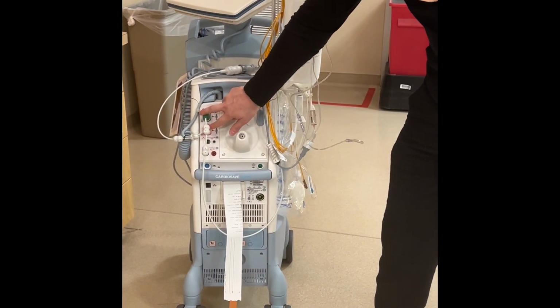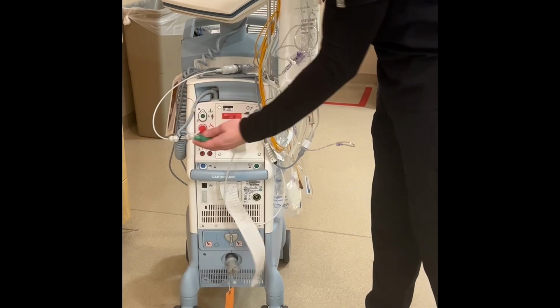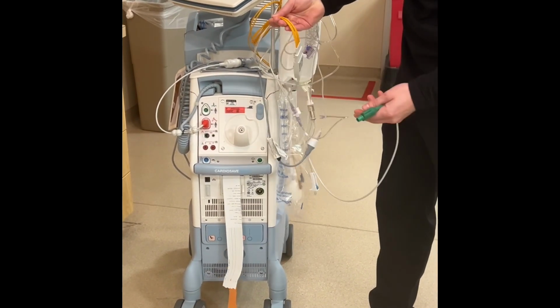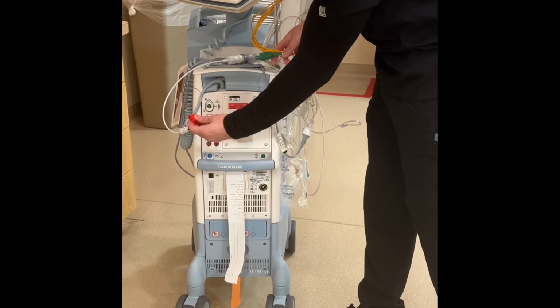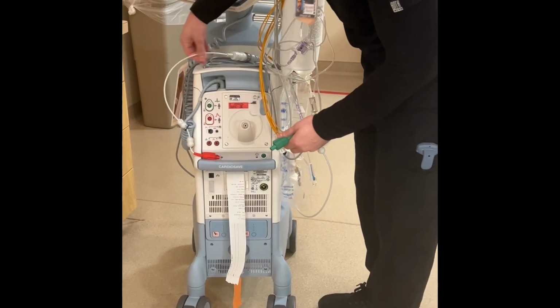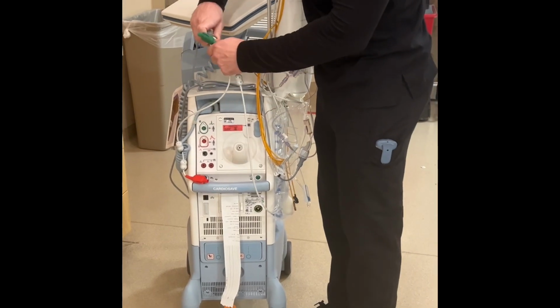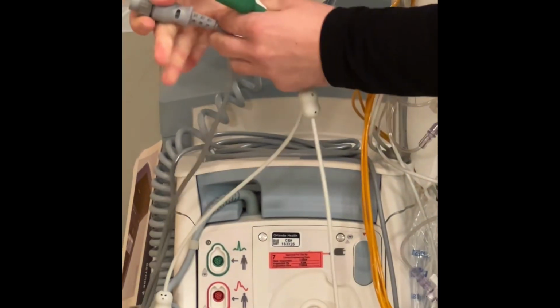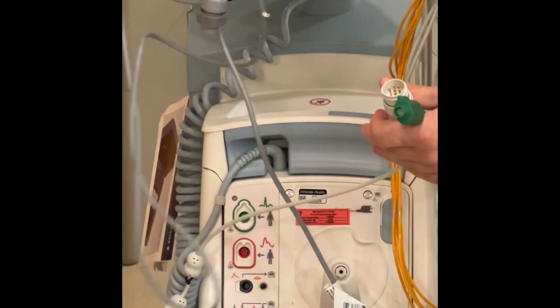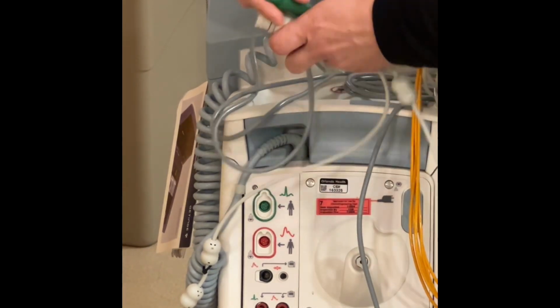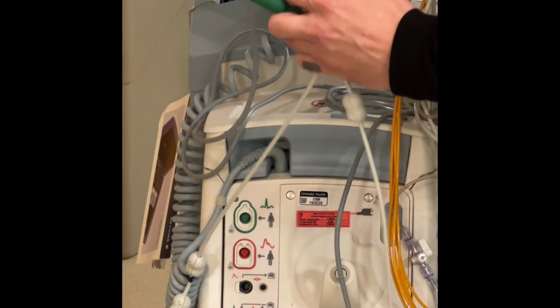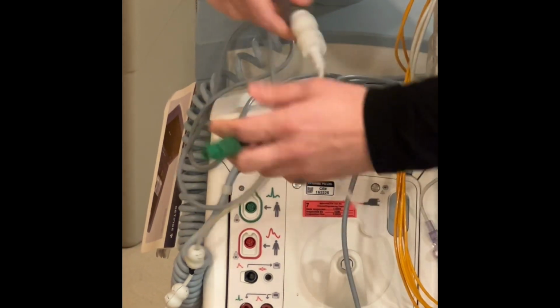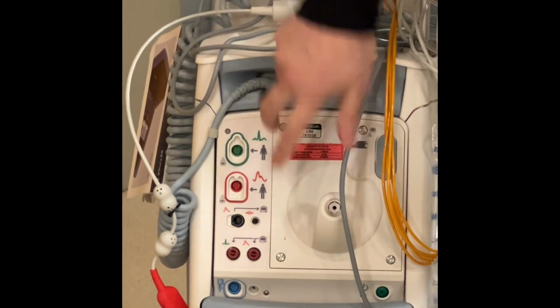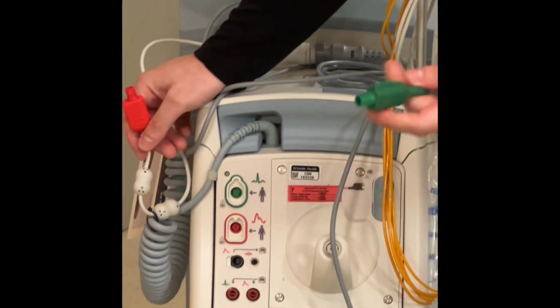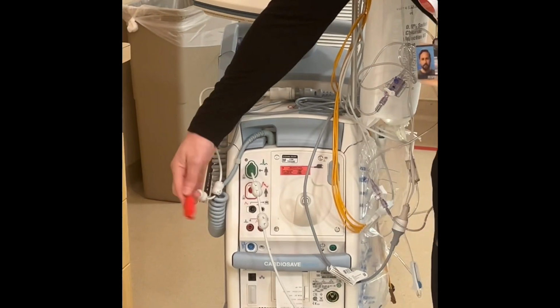You got two cables. The green one is your ECG, and then the red is your pressure. This one is an adapter, and it goes to your gray cable here. Looks pretty similar to the pressure cable that we use up in the ICU. This is usually sitting on the top of the machine. These are typically already connected. If they're not, go ahead and put these together. Let's twist down. These connections are usually already in place. If they're not, simply green to green, red to red.